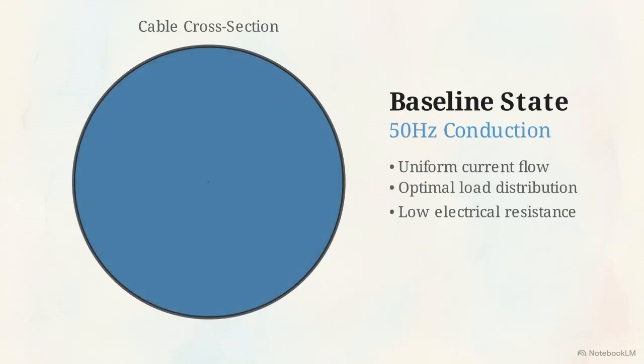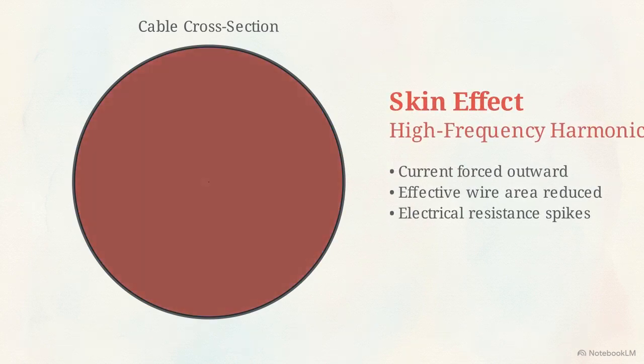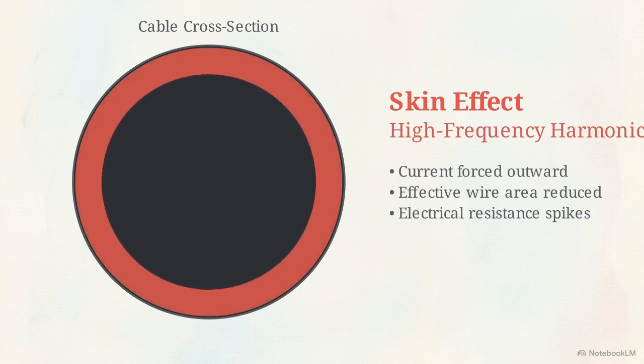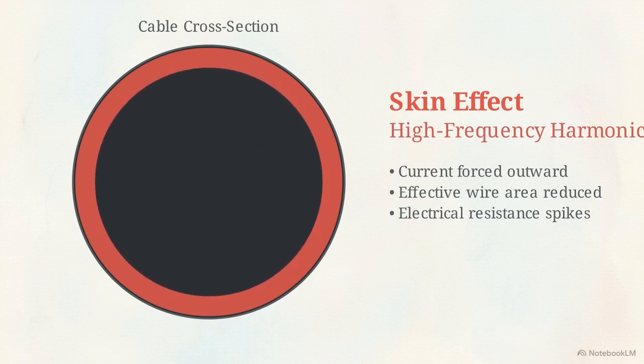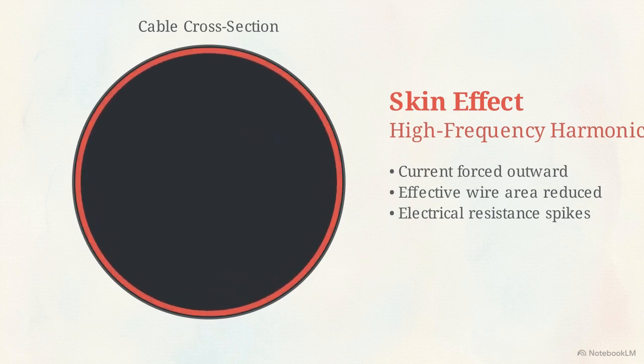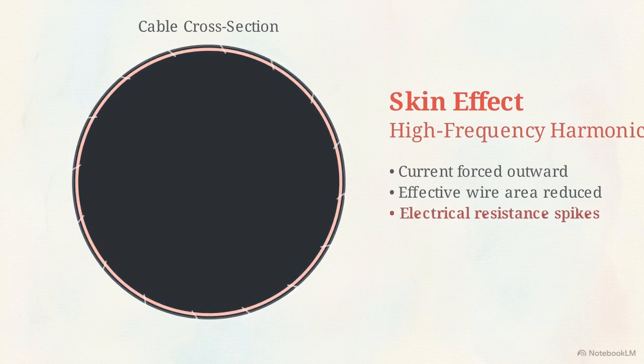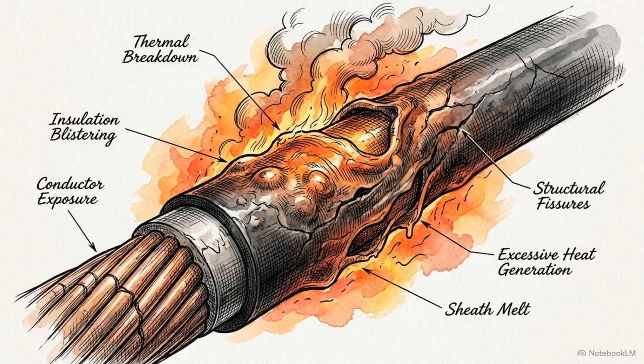To understand why this matters, we have to look at the physical copper and aluminum cables carrying this polluted power. A clean 50 Hz current flows evenly through the entire cross-section of a wire, distributing the load perfectly. But high-frequency harmonic currents behave differently. Due to the skin effect, these fast-moving frequencies electromagnetically push each other away from the center of the wire, forcing the current to crowd along the extreme outer edges. This effectively chokes the flow of electricity. It forces the same amount of power through a fraction of the space, which massively increases the resistance of the cable. That resistance creates intense heat.